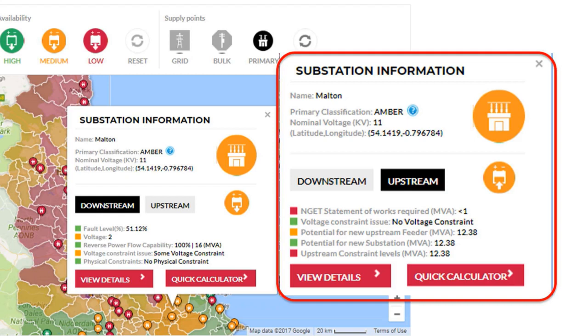If the 11 kV network had a tighter constraint on it, then the number that's green would be lower. Here we've got three boxes all saying approximately 12.5 MVA. Those numbers could be different, but the amount you can connect, the potential, will always be the lower number. So there's two boxes to look at there.